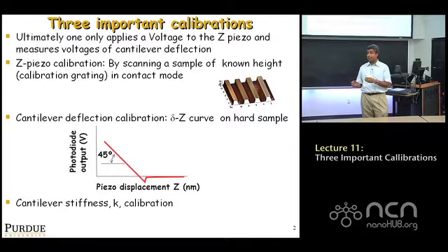Because in reality, what the AFM controller knows is that it applied 1 volt to the piezo. Now, how that 1 volt converts to a 10 nanometer Z displacement is not very clear. How do you know it for sure? It turns out most AFM systems have a conversion number inside them that converts the voltage they apply to the Z piezo into nanometers of piezo displacement. However, those numbers are not necessarily correct. So every time you do an experiment, preferably every month, you need to calibrate your Z piezo.